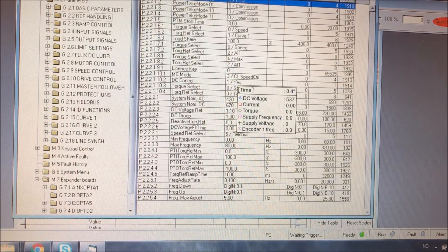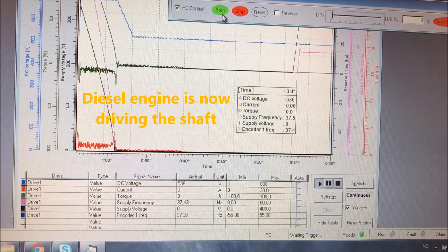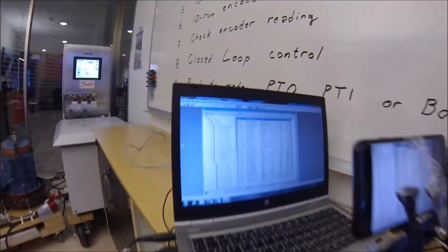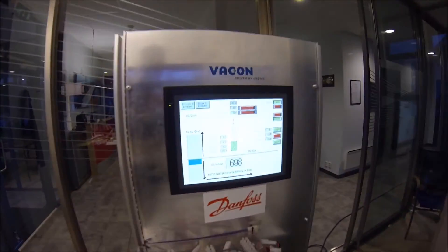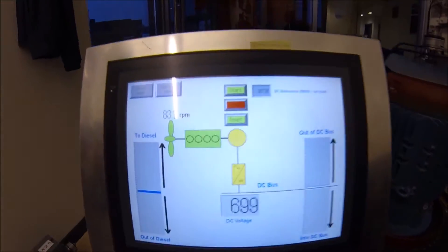Now the job for this drive is to produce DC. The drive is supposed to change the voltage to 700 volts DC. We are now in power take-off mode. The 700 volt DC is being produced by the active front end, which is connected to the city grid. The diesel engine is providing mechanical power to the shaft generator. We are now starting the generator application and it will contribute to the DC bus.